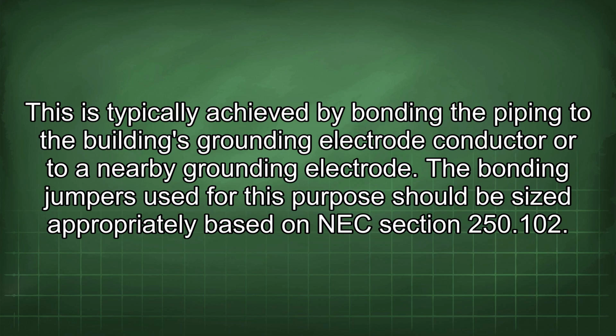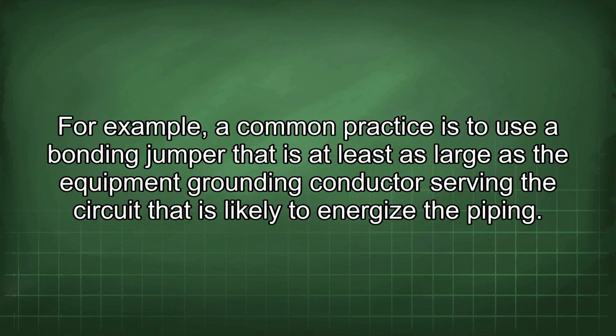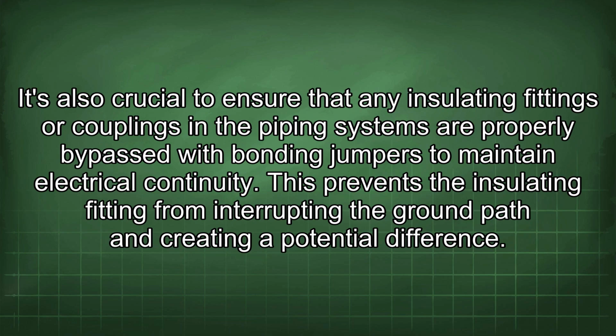This is typically achieved by bonding the piping to the building's grounding electrode conductor or to a nearby grounding electrode. The bonding jumpers used for this purpose should be sized appropriately based on NEC section 250.102. For example, a common practice is to use a bonding jumper that is at least as large as the equipment grounding conductor serving the circuit that is likely to energize the piping. It's also crucial to ensure that any insulating fittings or couplings in the piping systems are properly bypassed with bonding jumpers to maintain electrical continuity. This prevents the insulating fitting from interrupting the ground path and creating a potential difference.